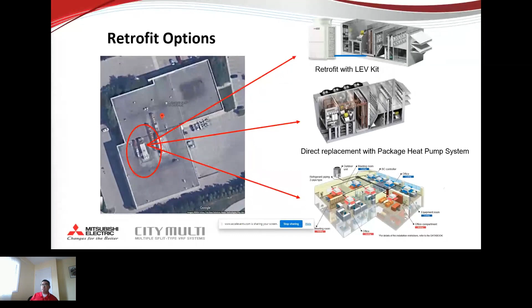The first one, usually the easiest one, is to retrofit with what we call a LEV kit. So just replace the internal box, the internal DX coil and the condenser with a VRF system, just having a VRF heat pump condenser provide heating and cooling. That will probably be the easiest system. We are still using the existing rooftop unit for the fan, the belts, etc. But again, the fan motor and the belt may not be up to date, right? So that is probably the most economic solution.